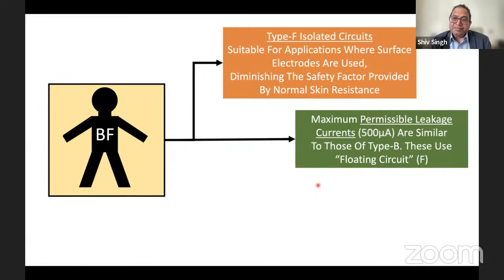But if you look at the maximum permissible leakage current, this is the same as type B. The difference is that type BF uses a floating circuit. That means there is no earth. So the definition of a floating circuit is a circuit that uses an isolation transformer. And what is it isolating from? From the earth. So it is earth-free. So you need to have equipment which uses an isolation transformer and is earth-free.